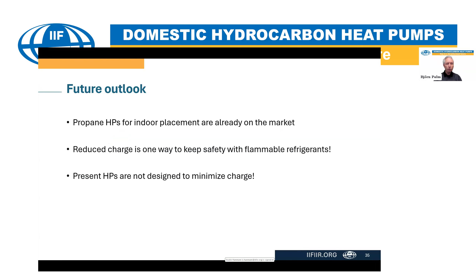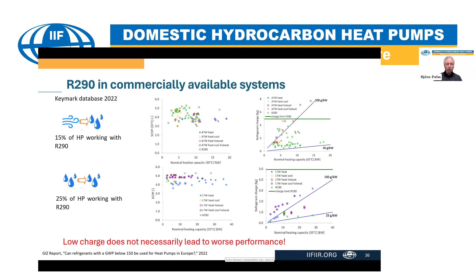But let me start going back to these slides which we saw before, and just want to point out that the heat pumps with the lowest specific charge are also the heat pumps with the highest COP. So there is no direct connection between low charge and COP. We can achieve very good COP even with a low charge. We'll talk a little bit more about that.